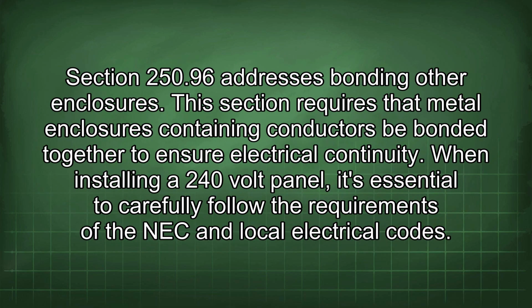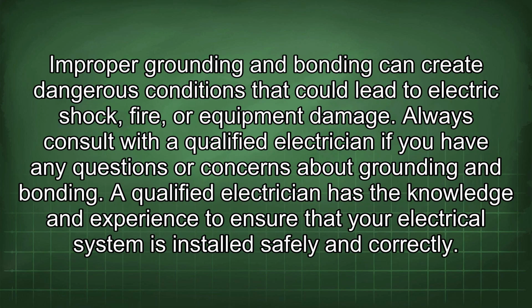Section 250.96 addresses bonding other enclosures. This section requires that metal enclosures containing conductors be bonded together to ensure electrical continuity. When installing a 240-volt panel, it's essential to carefully follow the requirements of the NEC and local electrical codes. Improper grounding and bonding can create dangerous conditions that could lead to electric shock, fire, or equipment damage. Always consult with a qualified electrician if you have any questions or concerns about grounding and bonding. A qualified electrician has the knowledge and experience to ensure that your electrical system is installed safely and correctly.